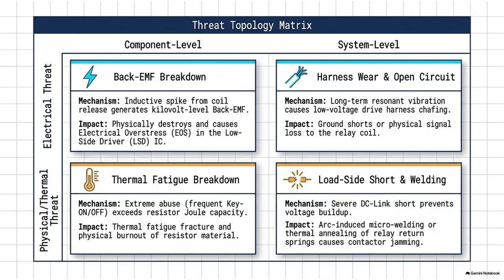Because this failure mode stems from the back electromotive force generated by the precharge relay's control coil. All right, so to contextualize this, you have to look at the low-voltage control side. The BMS motherboard uses a tiny 12-volt signal to energize a solenoid coil inside that precharge relay. And that coil creates the magnet that physically pulls the high-voltage contacts closed. Exactly. Now, energizing the coil is relatively benign. The real threat vector materializes when you turn it off. Wait, hold on. Turning it off is what causes the massive spike. Yeah, exactly. It's the whip effect of self-induction.